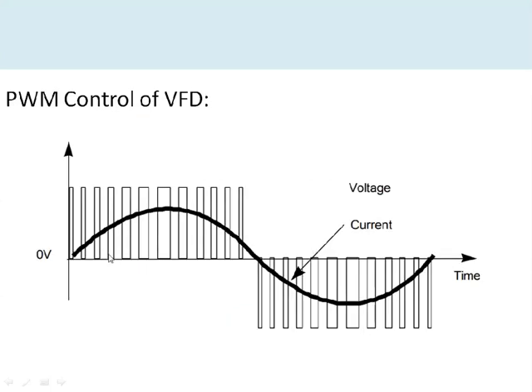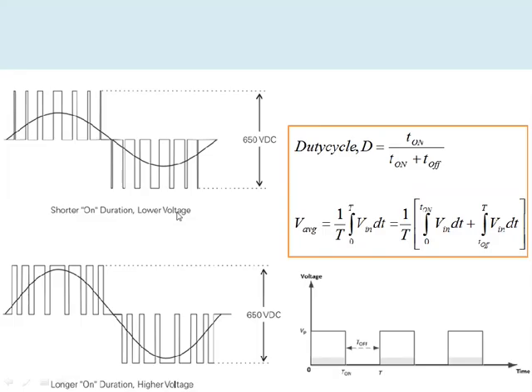This is the PWM control of the VFD. The on-off time duration of the pulses is varied — by varying this on/off duration, the voltage is varied. These voltage pulses are applied to the stator winding, which behaves as an inductor and opposes sudden changes in current. When a pulse is applied, a linear ramp is generated in the current, and these pulses are switched on and off such that a sinusoidal current is generated in the stator winding. The average voltage is given by V_avg = (1/T) × ∫₀ᵀ Vin dt.